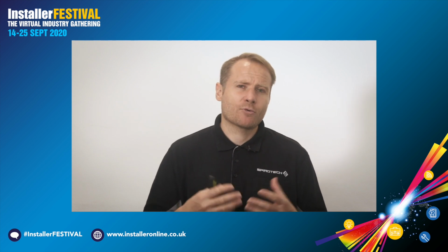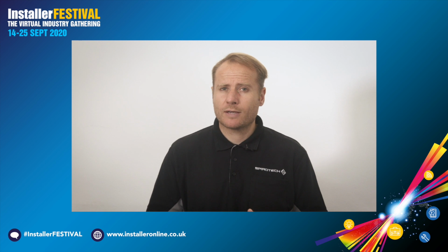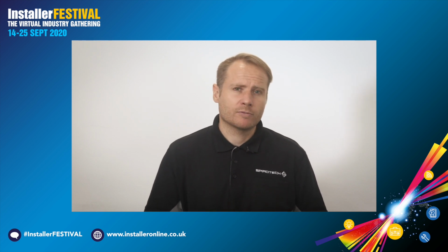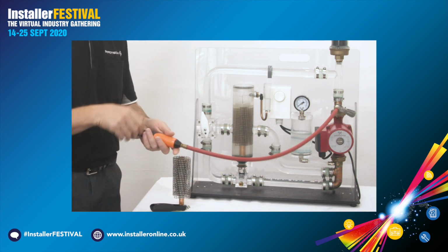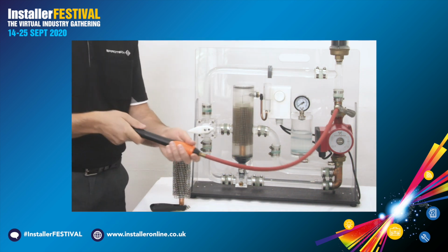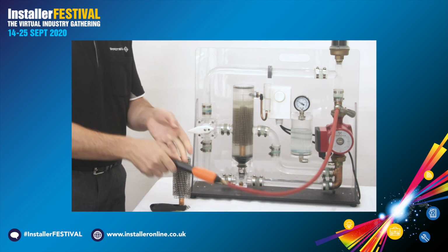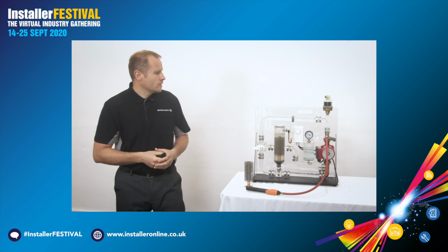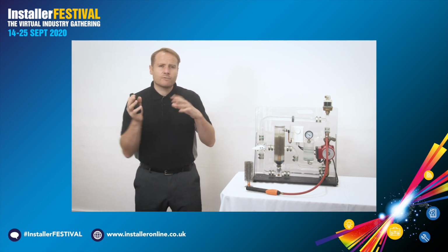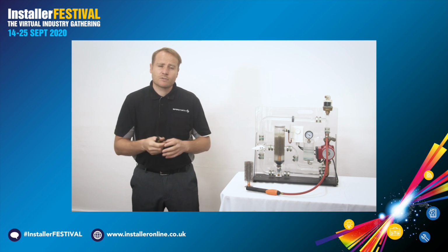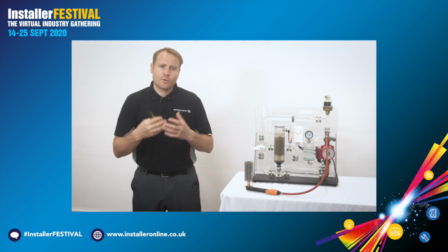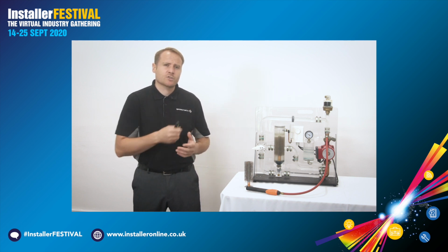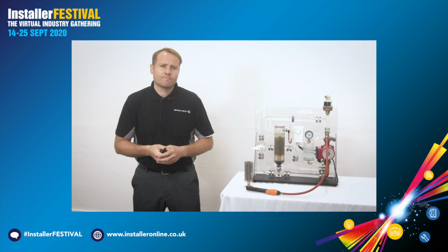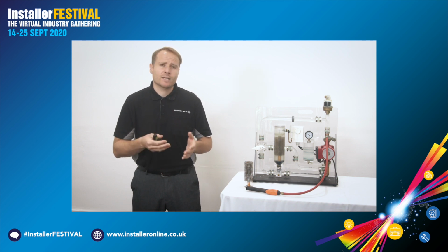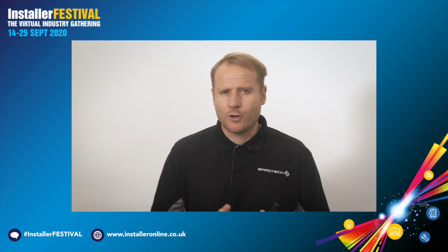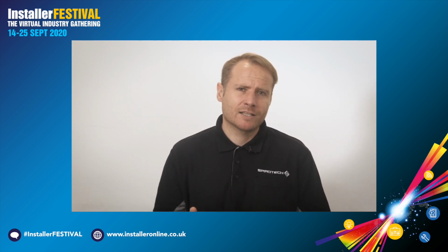But now let me show you an exaggerated scenario, because we know that air within pipework does restrict flow. We can see the water going fast, slow, fast, slow, fast, slow. And this is because, of course, as I mentioned before, the gases are creating a restriction in flow. Now, if a boiler was attached to this demonstration rig, the boiler would need to shut down because the heat would not be able to escape the heat exchanger quick enough. Now, if we run this through the deaerator, in no time at all, we can regain the intended or the designed flow.